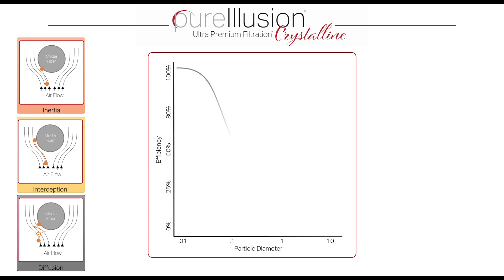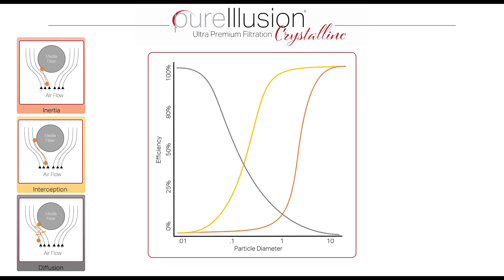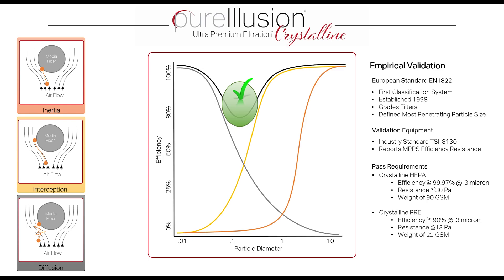We can see that in this graph. A particle of diameter 10 microns is not efficiently filtered by the diffusion principle alone, but looking at the interception or inertial impact principle, a 10 micron particle is certainly filtered out. These three principles intersect at a valley — a Goldilocks zone of 0.3 microns — where we perform our empirical validation based on the European standard EN 1822.